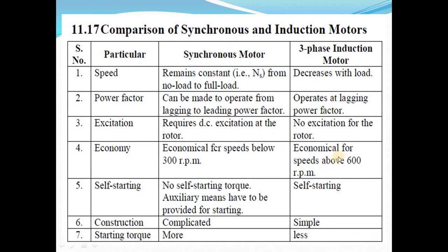The three-phase induction motor is economical for speeds above 600 RPM. If the speed is higher, then the three-phase induction motor is economical. If the speed is below 300 RPM, then the synchronous motor is economical. The fifth point of comparison is self-starting: there is no self-starting torque in the synchronous motor — auxiliary means have to be provided for starting — whereas in the three-phase induction motor there is self-starting torque. The sixth point is construction: the synchronous motor construction is somewhat complicated, while the three-phase induction motor construction is simple.